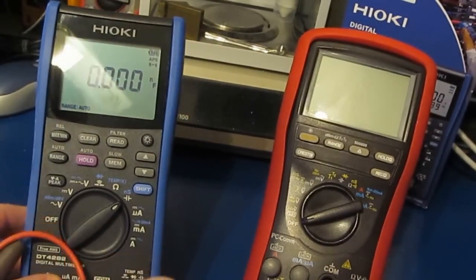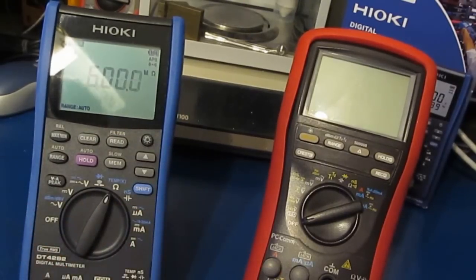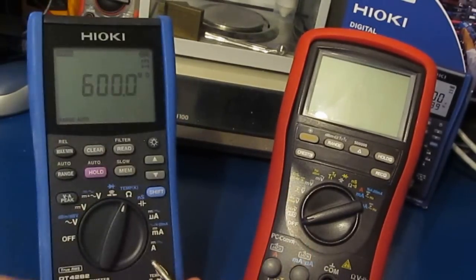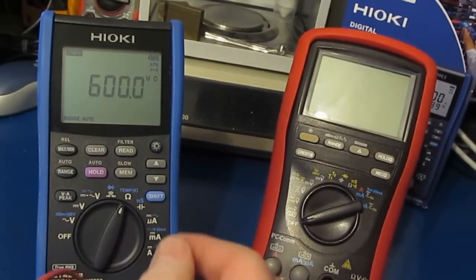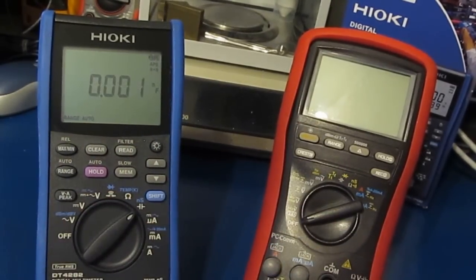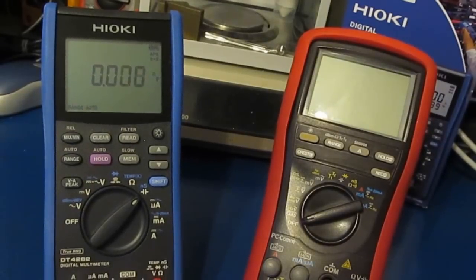Alright, let's just check the resistance real quick. Normally what you would see with the meters failing is it'll take out that high-speed clamp, and this would basically be reading some low resistance. The fact that it's reading high, it's a good indicator that the meter is not damaged.